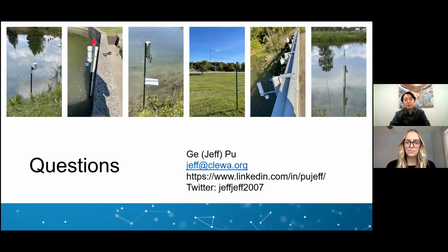But we are definitely using it in a very special case, because some of these sensors we have monitoring at a 5-minute interval, which is a lot of data. But if you tune down the monitoring interval, these sensors can easily last for 10 years or so in the field.